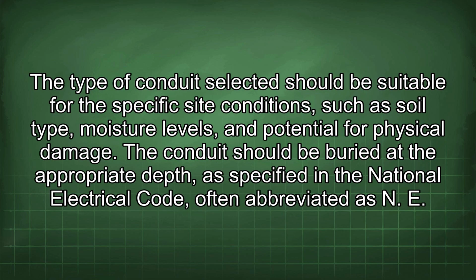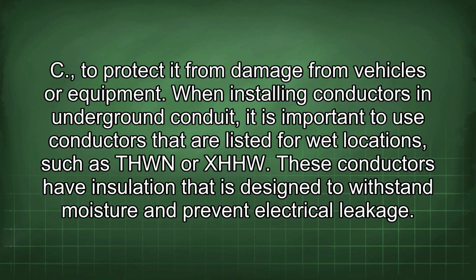The type of conduit selected should be suitable for the specific site conditions such as soil type, moisture levels, and potential for physical damage. The conduit should be buried at the appropriate depth, as specified in the National Electrical Code, often abbreviated as NEC, to protect it from damage from vehicles or equipment.